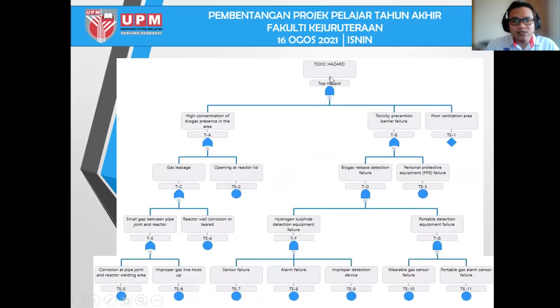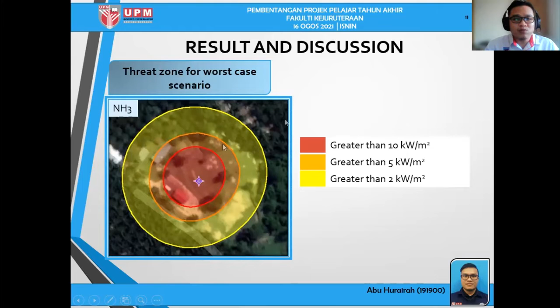So this is the result from the simulation that was done using ALOHA. The first one is to simulate the thermal radiation of methane if there is a dispersion of methane from the biogas from the anaerobic digester. So as we can see in the red threat zone area, the thermal radiation is greater than 10 kilowatt per meter square. In the orange area, the thermal radiation is between 5 to 10 kilowatt per meter square, and in yellow area, the thermal radiation is 2 kilowatt per meter square. So in the red area, it can be lethal since the thermal radiation is high and it can cause lethal burn to someone who is exposed to the thermal radiation.